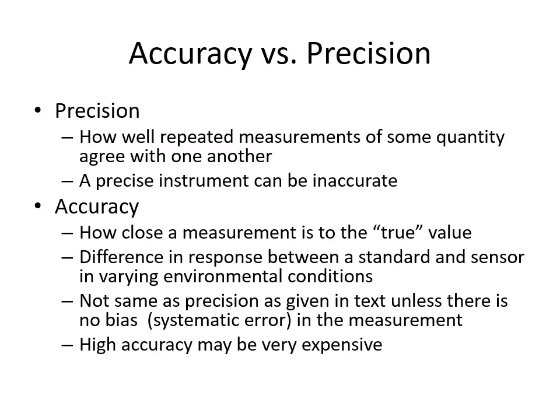Let's explain accuracy and precision. Precision is how close a bunch of measurements are to one another — a good trait if you get the same result given the same conditions. But a precise instrument can be woefully inaccurate. Accuracy is how close measurements are to the true value, which is unknown. We assess it by comparing our sensor's response to that of a standard across varying environmental conditions. High accuracy and high precision are not the same thing, especially if there's a systematic error, and high accuracy can be very expensive.